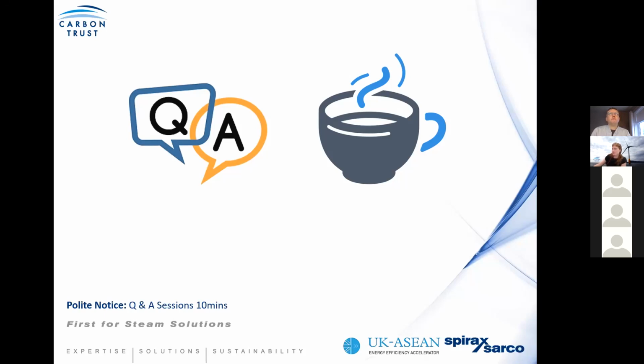A couple here on methods for checking steam traps. How many methods are there, and in your view what is the correct way to check steam trap functionality on site? Okay. The 2 common methods, I suppose, are a thermal imaging camera and ultrasonic. From our own experience, we would recommend the ultrasonic, the sound gun, because what a trap is meant to do is to depressurize condensate. We mentioned earlier that you would have high pressure condensate on one side of the trap and lower pressure condensate on the downstream side of the trap. So your thermal imaging gun is going to show that there's effectively a differential temperature across the trap.